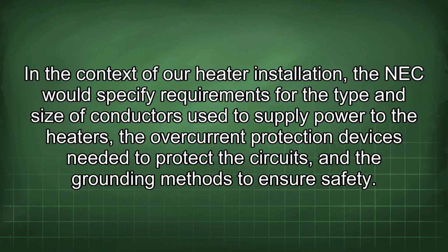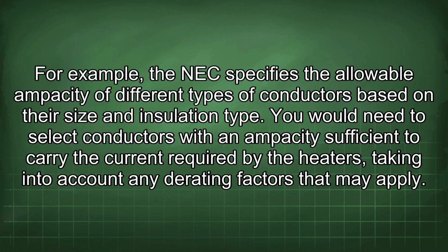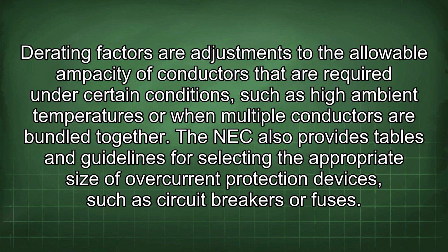For example, the NEC specifies the allowable ampacity of different types of conductors based on their size and insulation type. You would need to select conductors with an ampacity sufficient to carry the current required by the heaters, taking into account any derating factors that may apply. Derating factors are adjustments to the allowable ampacity of conductors that are required under certain conditions, such as high ambient temperatures or when multiple conductors are bundled together.